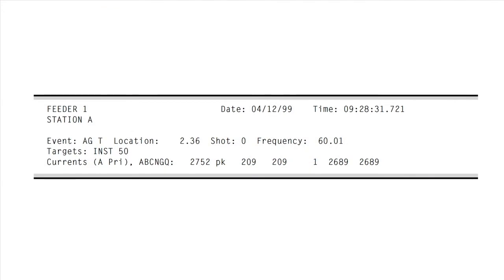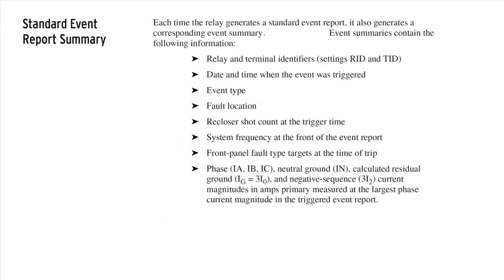Event reports. The SEL 351 offers 2 styles of event reports: a standard 15 or 30 cycle event report, or a sequential events recorder, or SER, report. Each time the relay generates a standard event report, it also generates a corresponding event summary. Event summaries contain the following information: relay and terminal identifiers, settings RID and TID, date and time when the event was triggered, event type, fault location, recloser shot count at the trigger time, system frequency at the front of the event report, front panel fault type targets at the time of trip, phase IA, IB, IC, neutral ground IN, calculated residual ground, and negative sequence current magnitude in amps primary, measured at the largest phase current magnitude in the triggered event report.